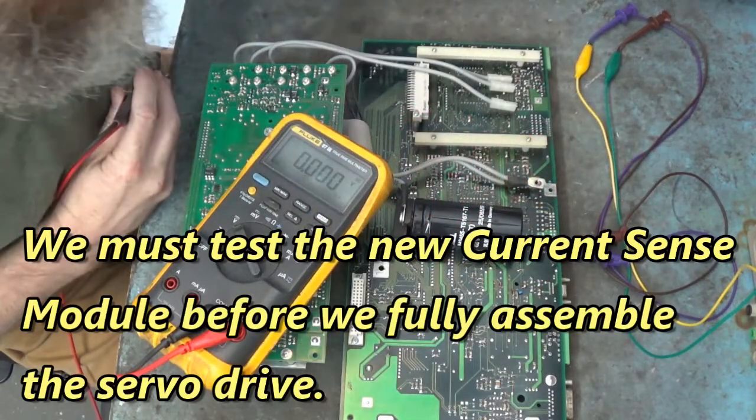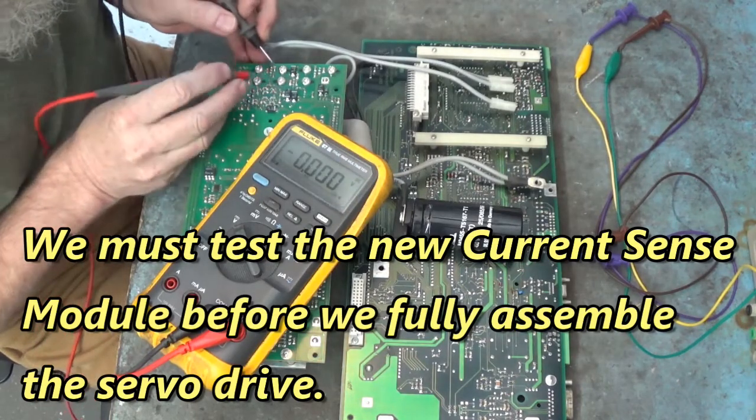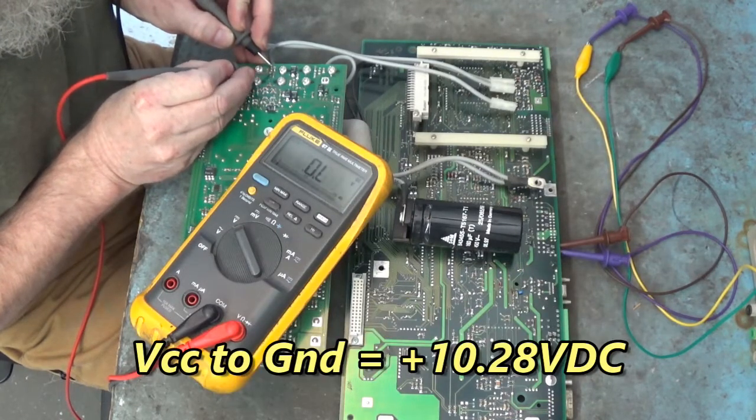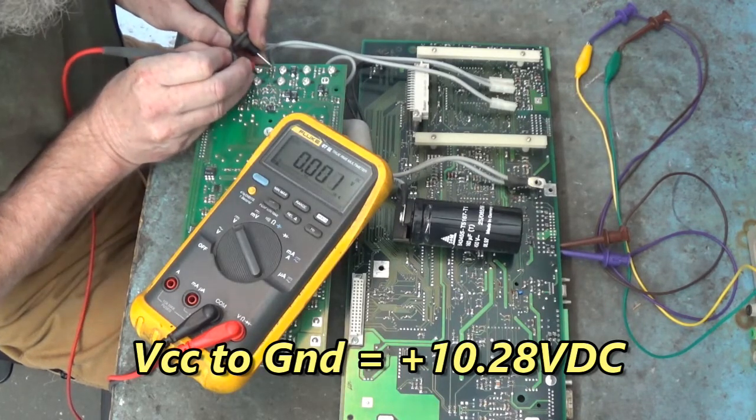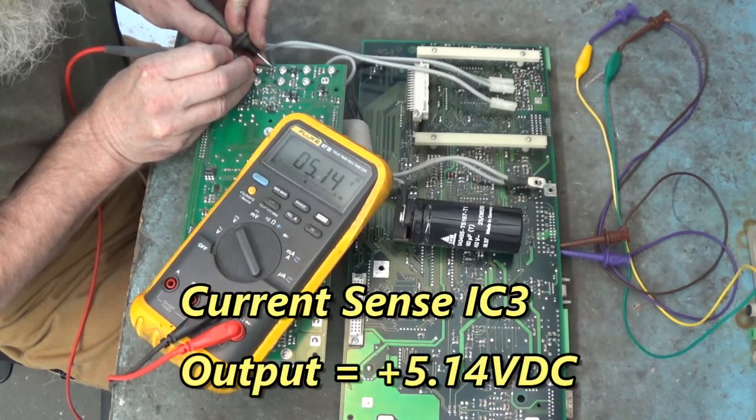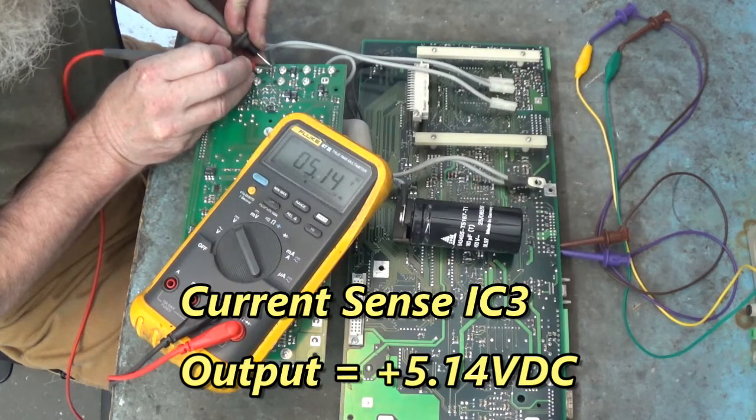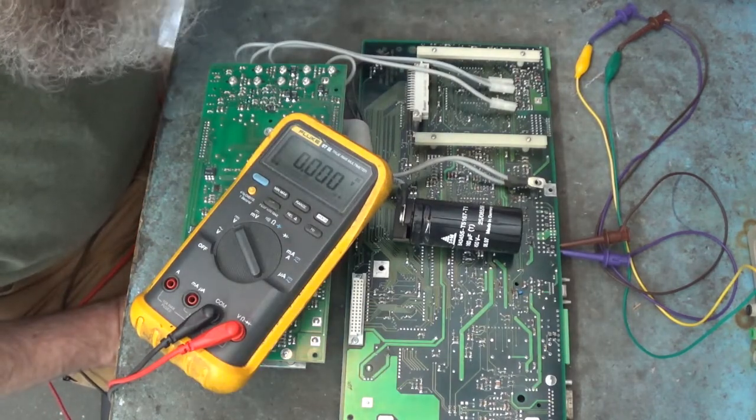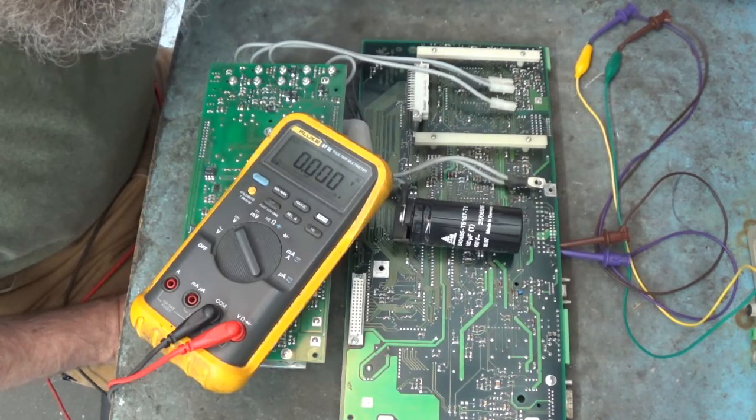Now we're going to look at that current sense output. It should be 5, not 9. There's our VCC to ground, 10.28 volts DC. Here's the output. 5.14 volts DC. It's not 9 volts anymore. We'll put the drive back together. See if it boots up good. See if we fix that alarm 61 fault.